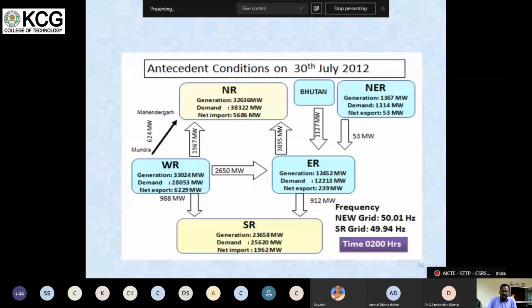Without frequency synchronizing, we cannot take power or send power to another region. So from the western region it was connected through HVDC. From the eastern region also, the southern region was connected with DC lines. At that time, at 2 o'clock, the frequency is 50.01 and in the southern region 49 point something. The southern region was a little lower. Okay, this is the condition.